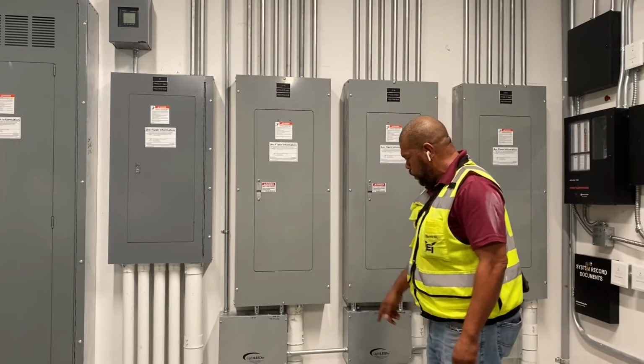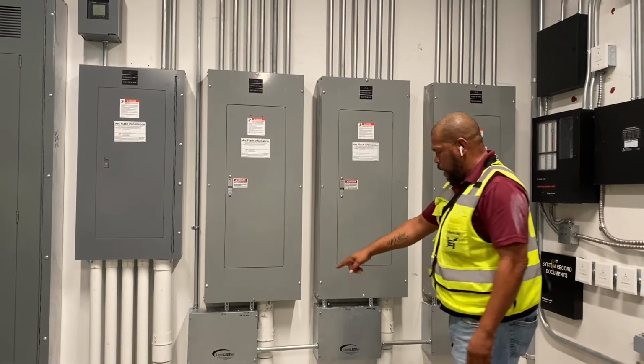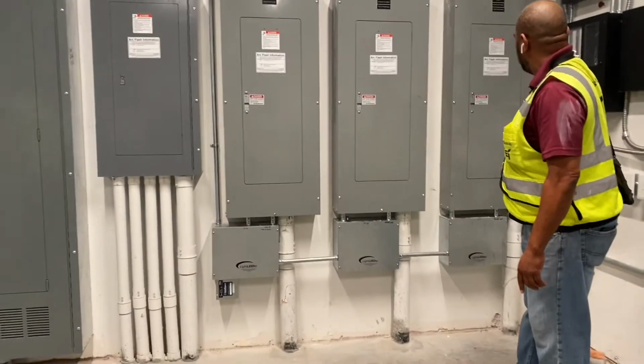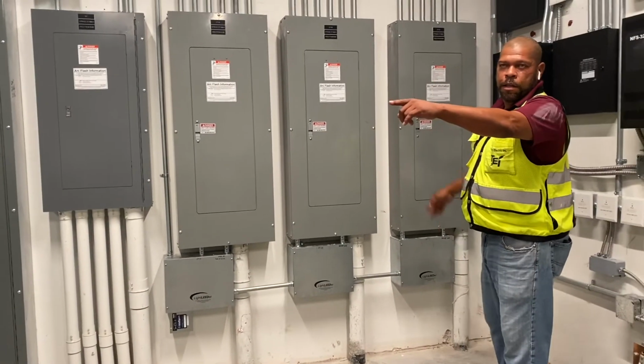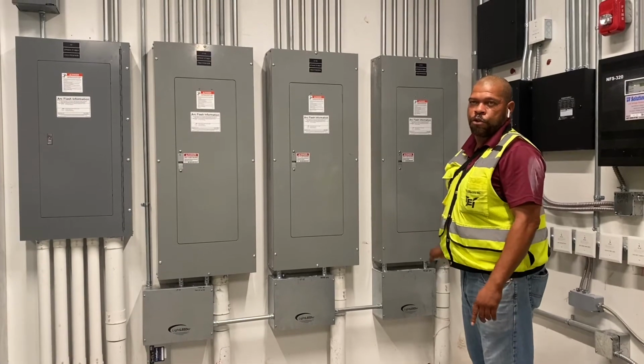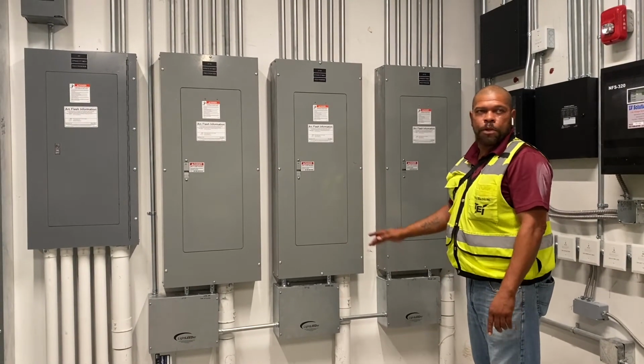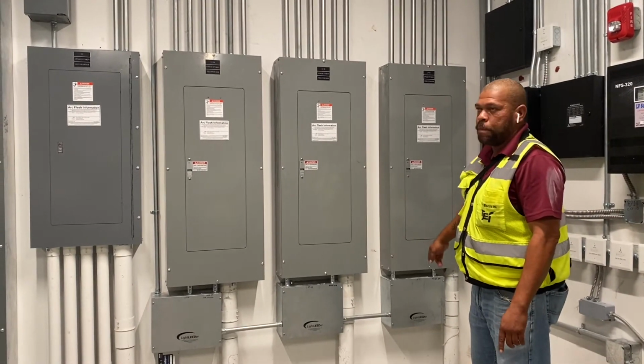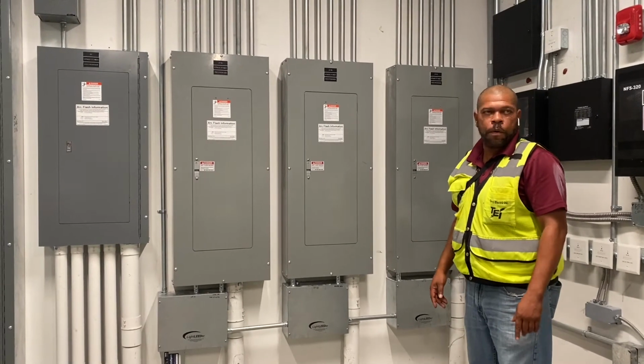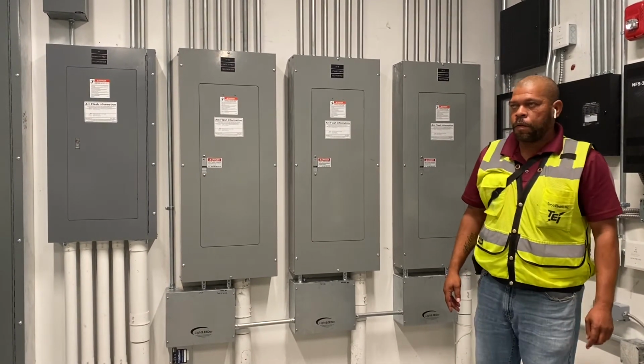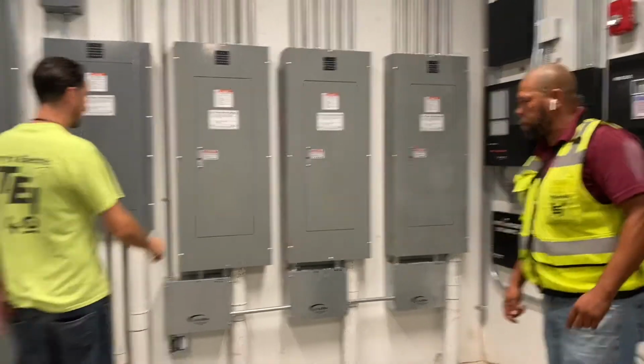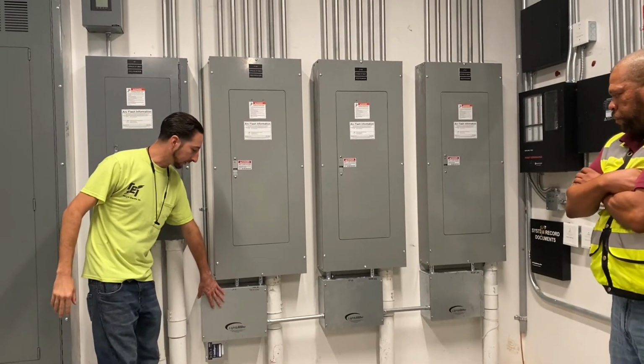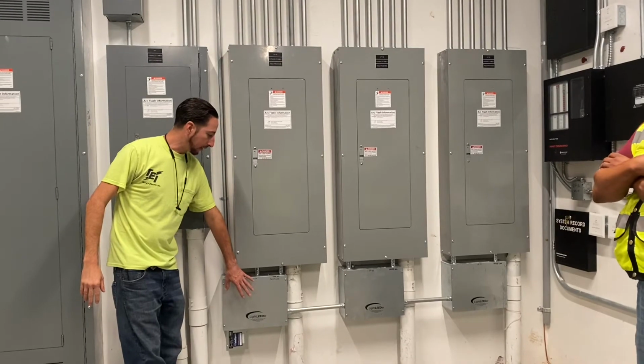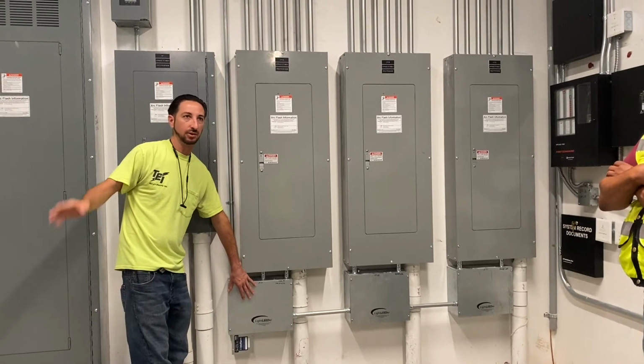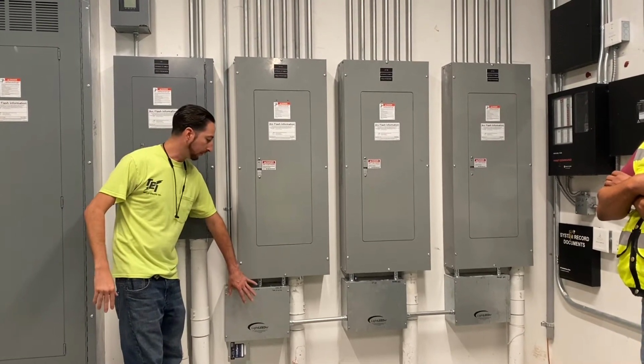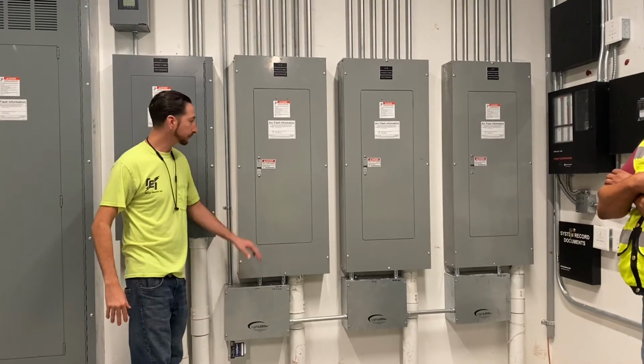All these panels here, when you see any of these panels that have these boxes on the bottom, these panels are all lighting control panels. So anytime you see a panel with them bottom things on there, that means that's your lighting control. I can explain a little bit about this while we're in here. So basically, this is a processor, and this will get all the commands from the switch stations around the first floor or whatever load is associated on the panel.